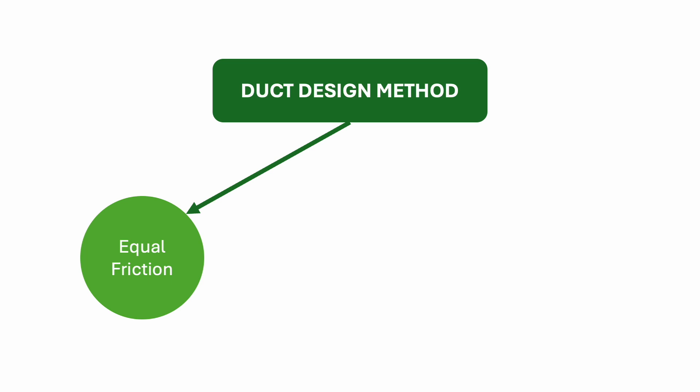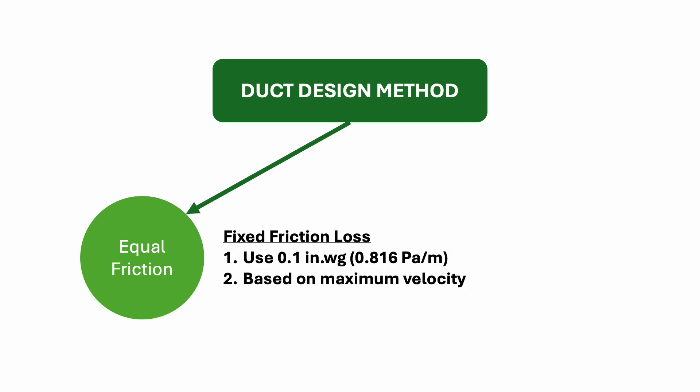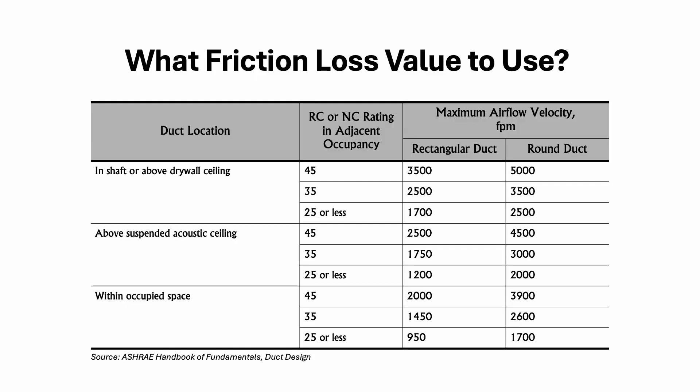For this method, we use a fixed friction loss to size our duct. We can either use the 0.1 inch water gauge or based on the maximum velocity. To figure out what friction loss value to use, we can refer to this table.